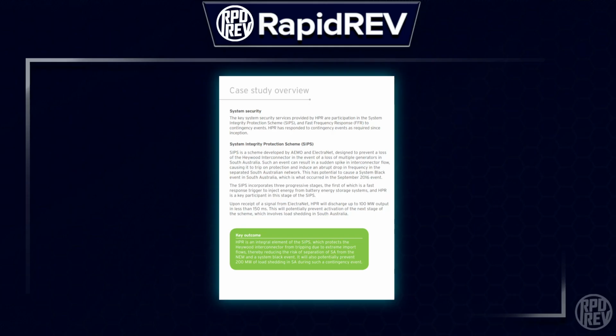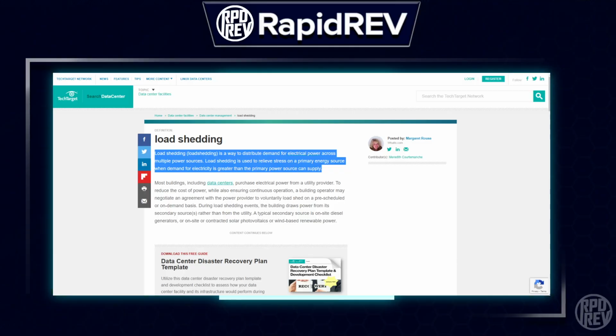System integrity protection activates when, say, some generators go offline unexpectedly in a power plant, and there's suddenly way less power input to the grid. Because grids are interconnected, this could cause a surge of energy into the affected parts of the grid. When a surge like that happens, parts of the grid will trip to protect itself and start load shedding.